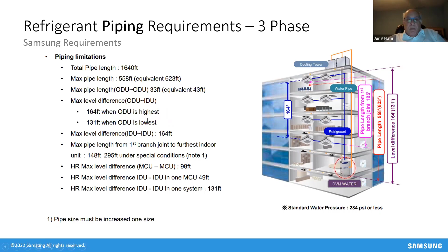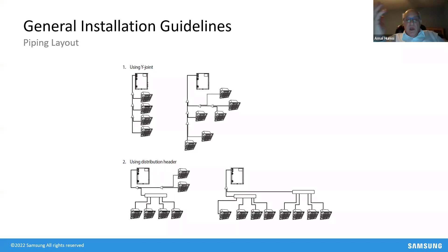The way we connect the units is you have the outdoor unit and then you have refrigerant piping. And we have Y joints that connect the different units to the outdoor unit, or you can use headers. So basically you get the refrigerant to either a 4-port or an 8-port header, and then you connect the units to those headers. That is on the heat pump system. If it is a heat recovery system, we have what is called a MCU, and basically that is a refrigerant traffic cop that decides which unit requires heating, which unit requires cooling, and it sends the appropriate, either hot gas or liquid, to those particular units. And that's how you are able to heat and cool at the same time.